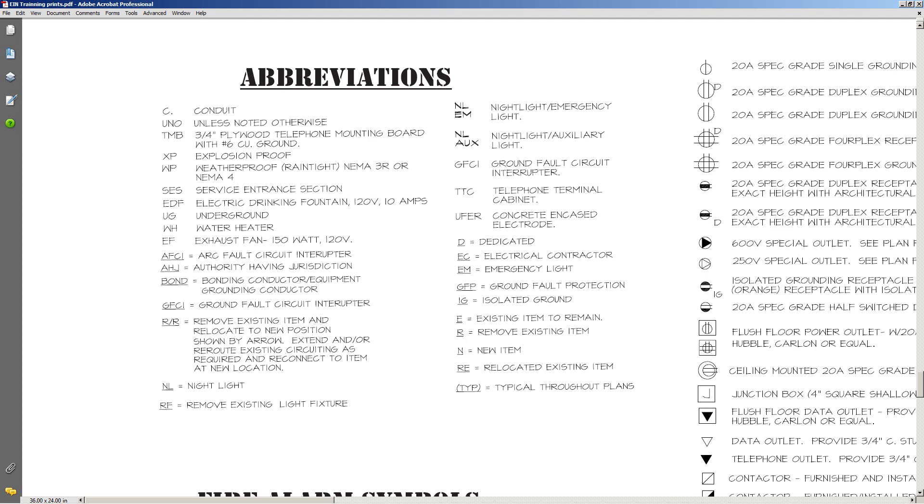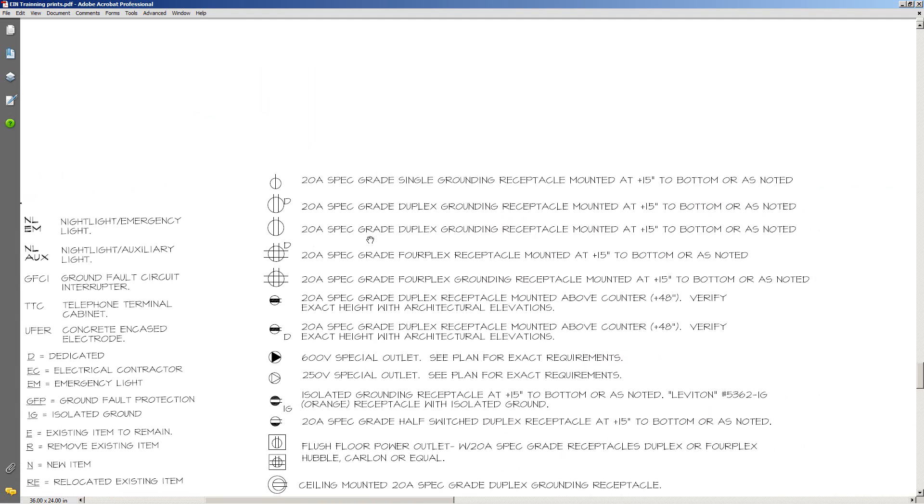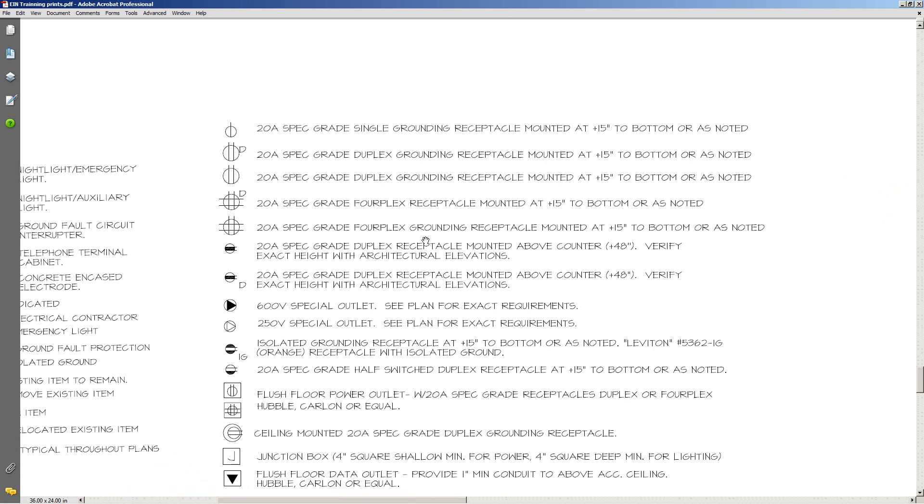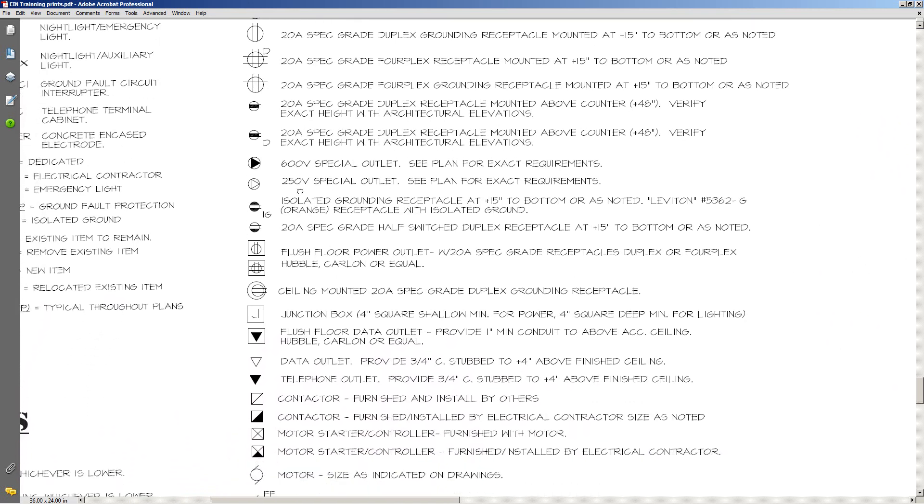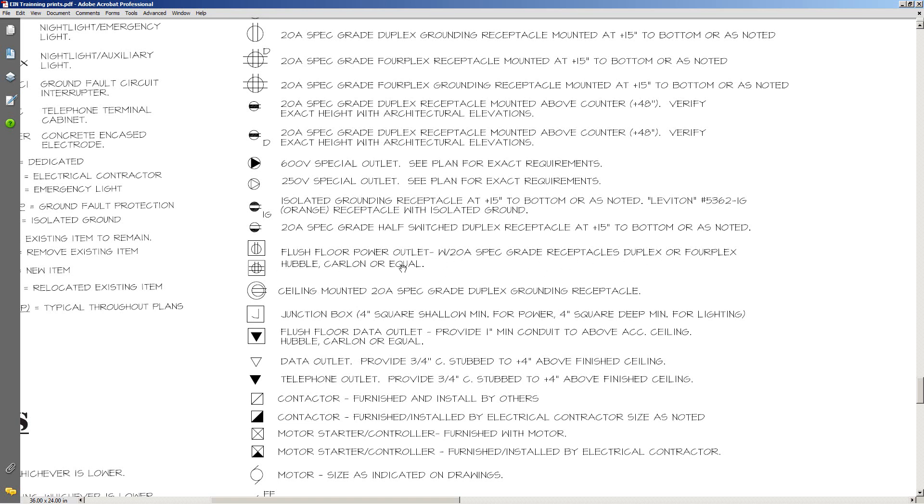And then we'll take a look over here at some more. You've got some 20 amp outlets, spec grade, this is pretty generic here. There's more 20 amp, now we're going to get into special outlets, 600 volt special outlet, 250 volt special outlet. As always, see plan for exact requirements on that one. You've got some floor boxes. In this particular case here, it's spelling out Hubbell, Carlon, or equal. Well price-wise, depending on what job you're on, you're going to go with equal.